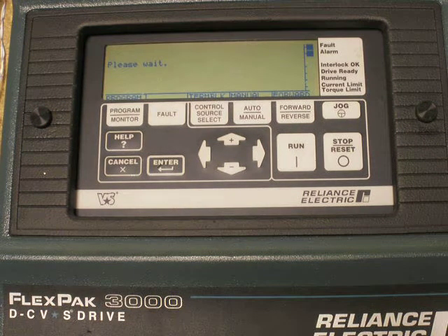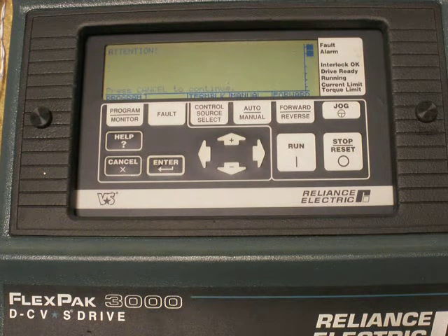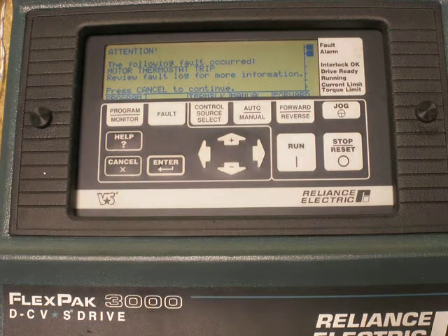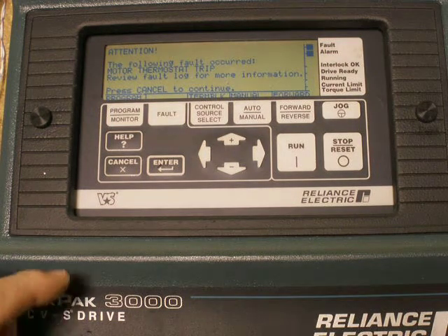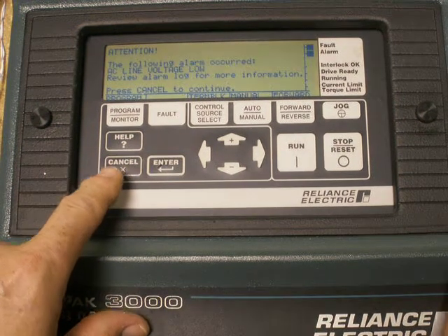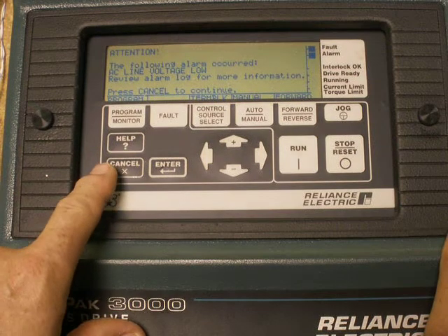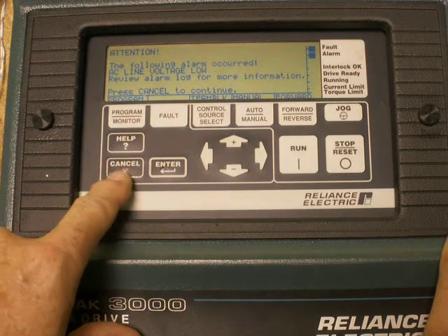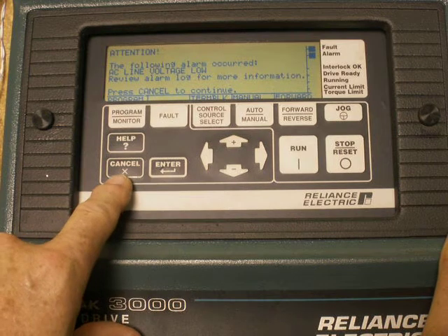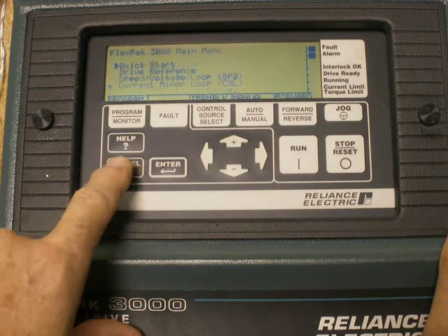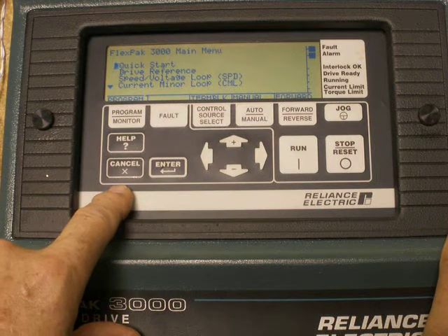It's about finished initializing. At this point, we've come up with a motor thermal trip because the motor is not connected — we're going to cancel that fault. We've also got an AC line voltage low, due to the fact the drive is not hooked up with the correct power; we're just powering directly into our power supply. We're going to cancel that fault.